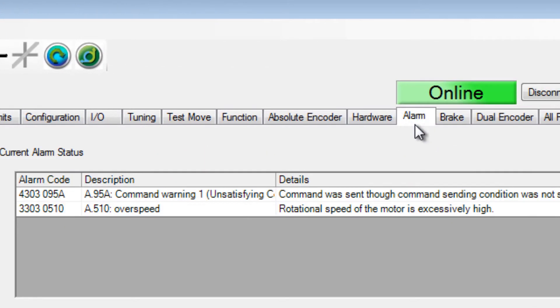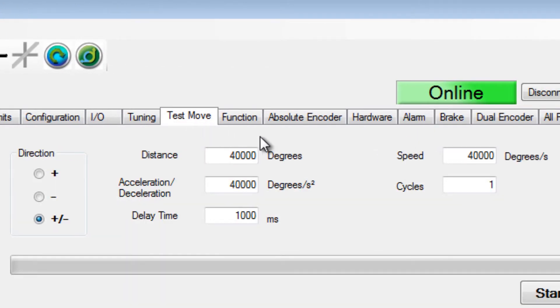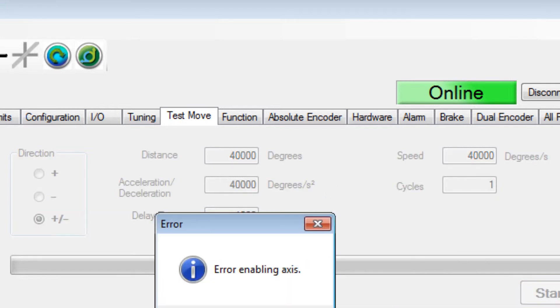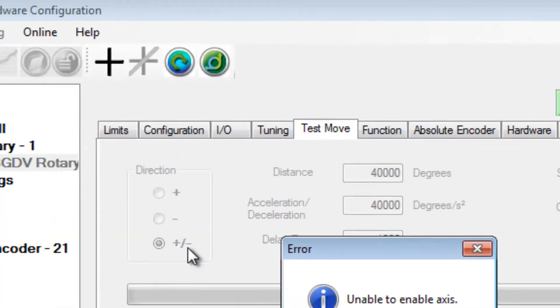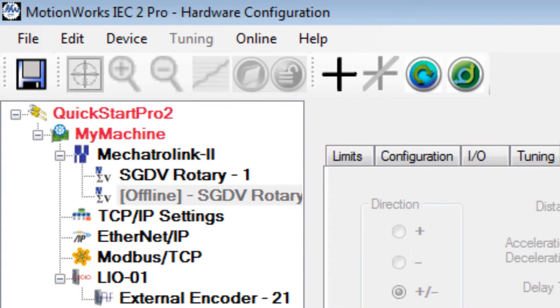If you click on the alarm tab, you can see this alarm. If you're in the test move and the axis doesn't enable, it may be because that axis does have an alarm, and the axis may go offline as you see here in the tree.